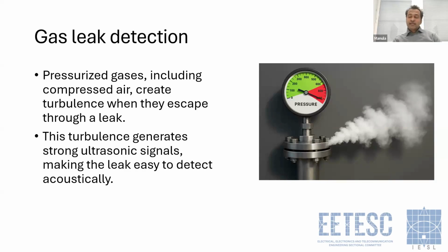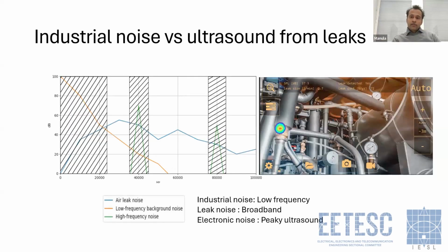This is a fairly straightforward application, I would say, compared to partial discharge, because in partial discharge we have these PRPD patterns and it is tricky to differentiate things, but gas leak detection is straightforward in that sense. But the tricky thing is that, if you compare these two applications, we normally detect partial discharges in silent environments. In general, we don't have that much noise in outdoor air insulated substations. In contrast, here we try to detect gas leaks in noisy industrial environments, for example power plants or production facilities.